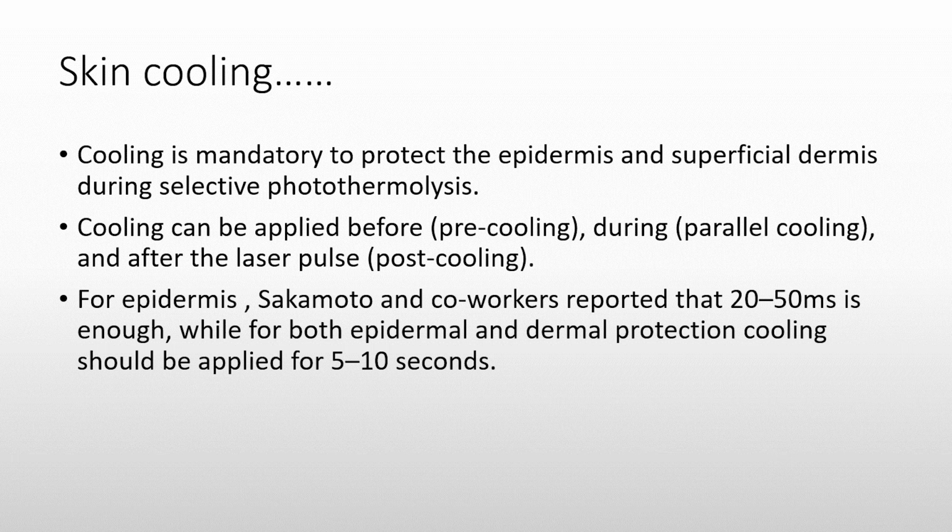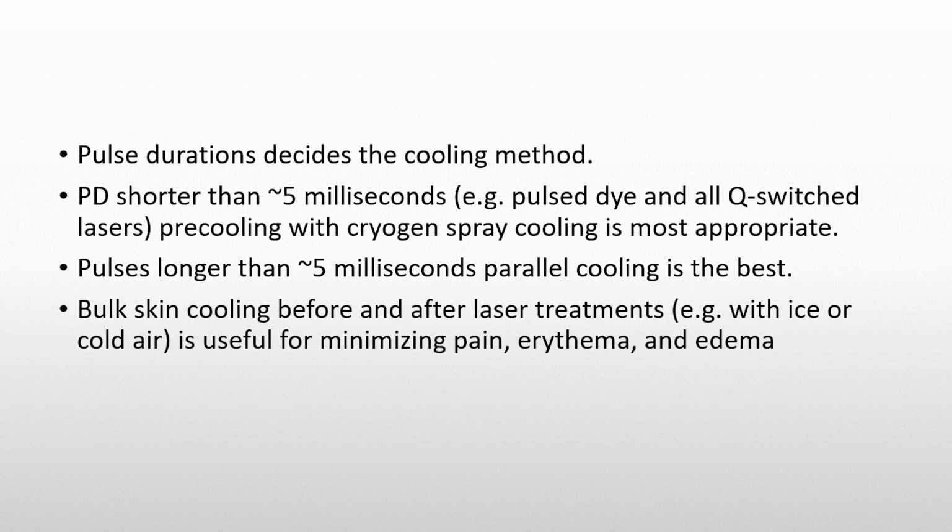Pulse duration decides the cooling method. For a pulse duration shorter than 5 milliseconds, such as in Q-switched lasers, pre-cooling with cryogen spray cooling is the most appropriate method, while for a pulse duration of more than 5 milliseconds, parallel cooling is the best. And bulk skin cooling is used to minimize the pain, erythema, and edema following the treatment.